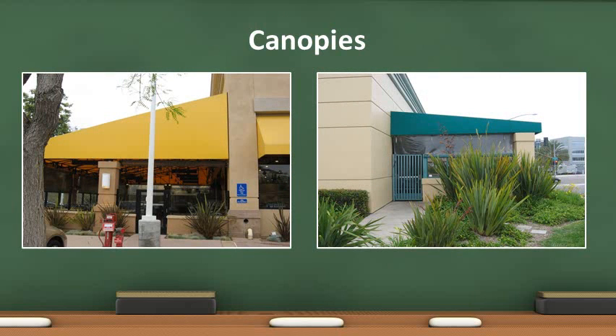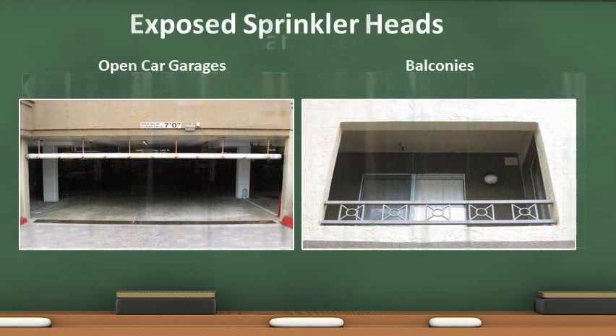Sprinklers shall be installed under exterior roofs or canopies exceeding 4 feet. When the canopy or roof is of non-combustible construction, sprinklers can be omitted. When combustibles are stored and handled under roofs and canopies, sprinklers shall be installed. When installed in open car garages, within 20 feet of building openings, balconies, and patios, sprinkler heads shall be listed for corrosion resistance, such as Teflon or wax coated or stainless steel.